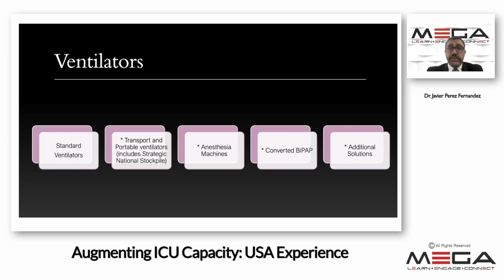It also requires changing some of the circuits and filters continuously, which is not typically what we do in the ICU with our ventilators. They're also limited as far as the operator. Not all anesthesia machines can be used, number one. Number two, not everyone might be able to handle them properly. And number three, it requires more maintenance and experience than ventilators. So ICU personnel are typically not qualified to manage anesthesia machines, and that becomes a bit of an issue.